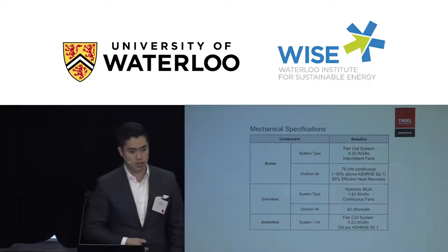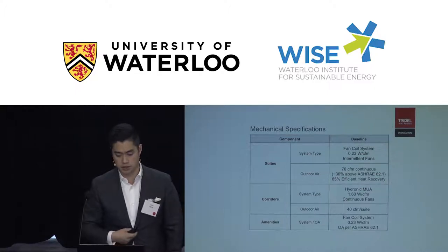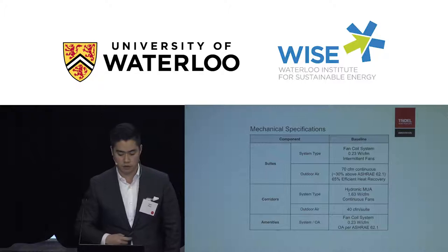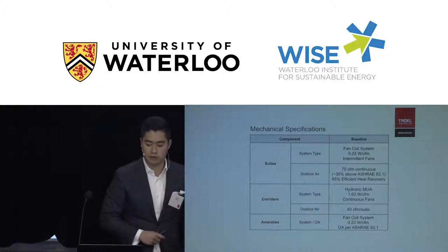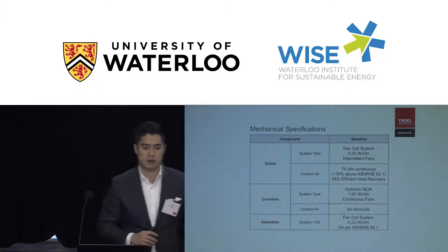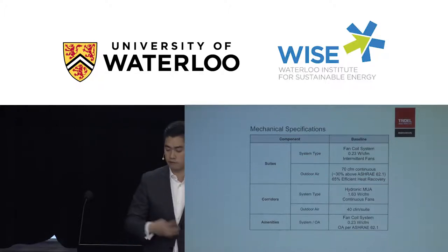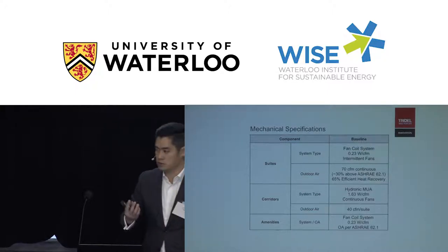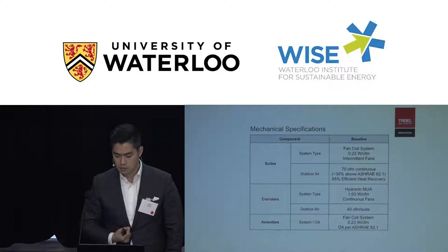That's effectively how we heat and cool our buildings today as well. Typically you'll see a central plant with centralized boilers, centralized chiller plants with chillers, condenser pumps, cooling towers, and so on. That gets pumped into fan coil systems distributed throughout the suites. It's not like a single family home with a forced air system—forced air is not a very effective way of distributing energy in a 30 or 40 story building, so instead we rely on water.